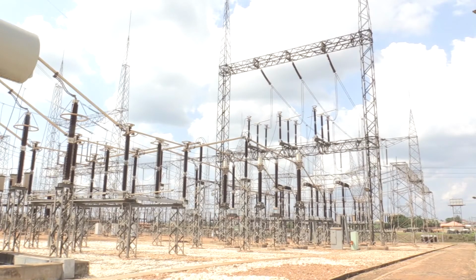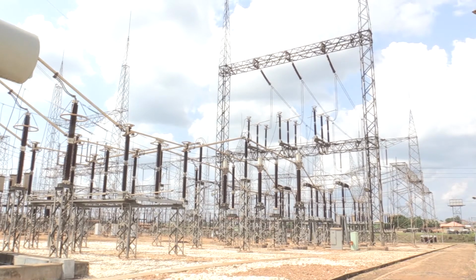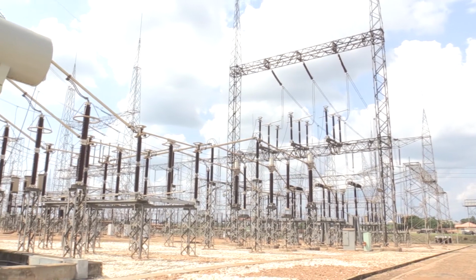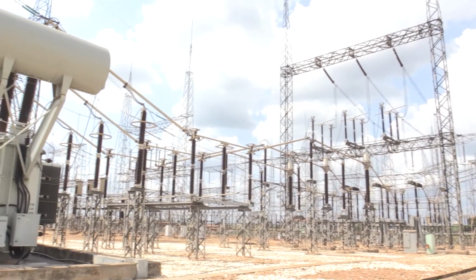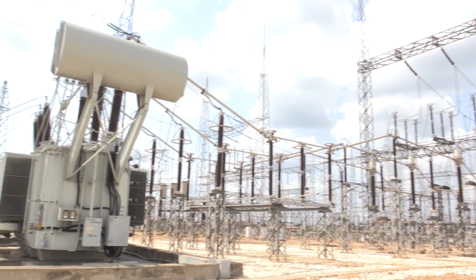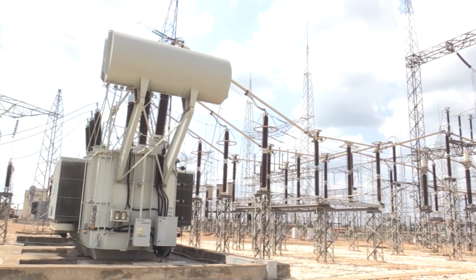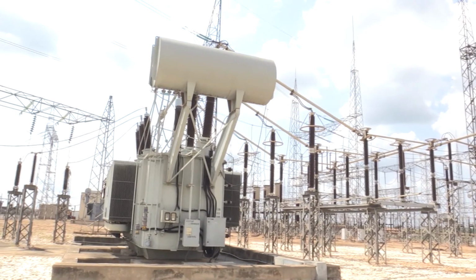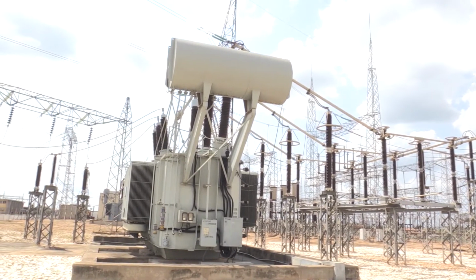We have a lot of projects that are ongoing. Let me start with the ones at Ajaokuta, which are almost finishing. At Ajaokuta, we have the Obajana substation, which is a construction of 2 by 150 MVA, 330/132 kV, and then 2 by 60 MVA, 132/33 kV.